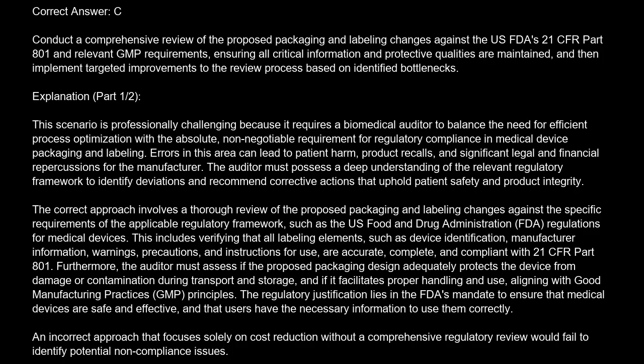The correct approach involves a thorough review of the proposed packaging and labeling changes against the specific requirements of the applicable regulatory framework, such as the U.S. Food and Drug Administration, FDA regulations for medical devices. This includes verifying that all labeling elements, such as device identification, manufacturer information, warnings, precautions, and instructions for use, are accurate, complete, and compliant with 21 CFR Part 801. Furthermore, the auditor must assess if the proposed packaging design adequately protects the device from damage or contamination during transport and storage, and if it facilitates proper handling and use, aligning with good manufacturing practices, GMP principles. The regulatory justification lies in the FDA's mandate to ensure that medical devices are safe and effective, and that users have the necessary information to use them correctly.